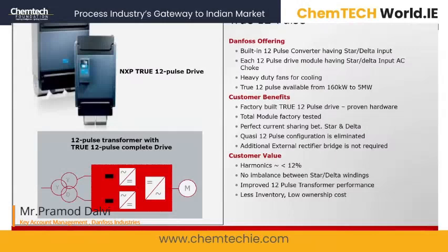So Danfoss drives has a true 12 pulse design. That means our drive has star and delta configuration with 2 diode bridges built in, whereas our competitors give 2 different drives and make a 12 pulse design. But this will have an effect if both the loads are different, and there can be a circulating current flowing through the transformer. So a built-in 12 pulse converter is called true 12 pulse in industry terminology.